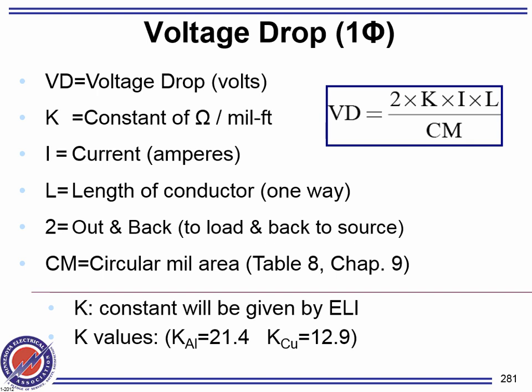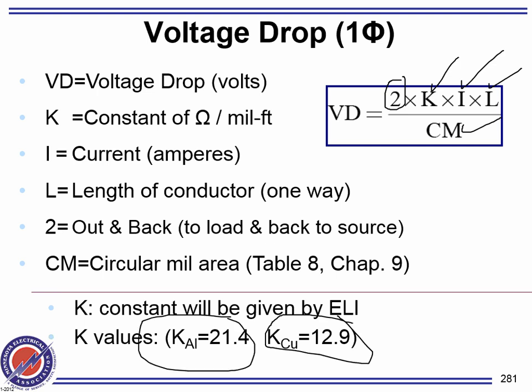Voltage drop is kill over CM. Remember that, kill over CM? What happens if this is a 3-phase? What do you do with the 2, and what do you put there instead? 1.732, because of 3-phase. L is length in feet, not meters. I is current in amps. CM is cross-sectional area. Well, it's not really. It represents the size of the conductor in circular mils. K is a factor of the impedance, the resistance of the conductor, the wire. You shall not remember these, but typically they are 21.4 for aluminum and 12.9 for copper.